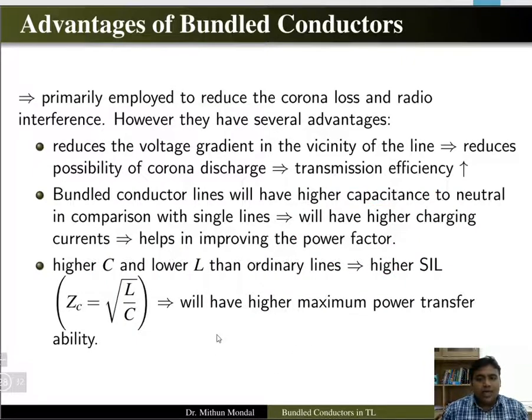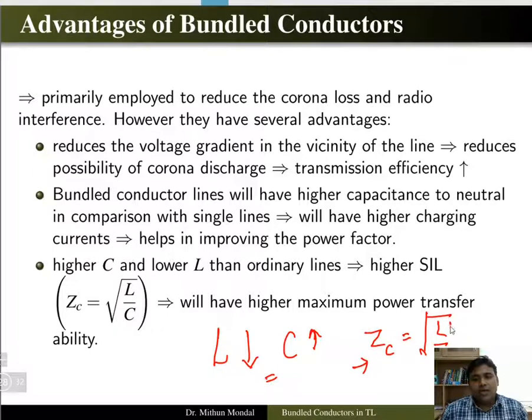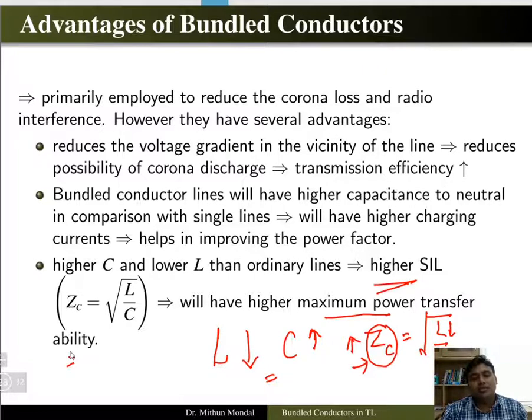We have reduced inductance and increased capacitance using bundle conductors. There is a term known as surge impedance, which is √(L/C). If we reduce L and increase C, the surge impedance of the line will decrease, meaning higher surge impedance loading — so the maximum power transfer capability of the line will increase.